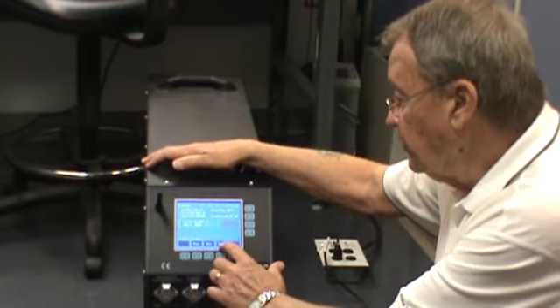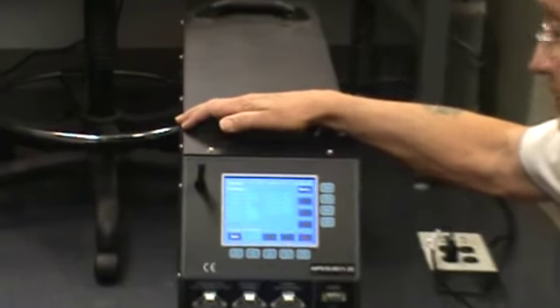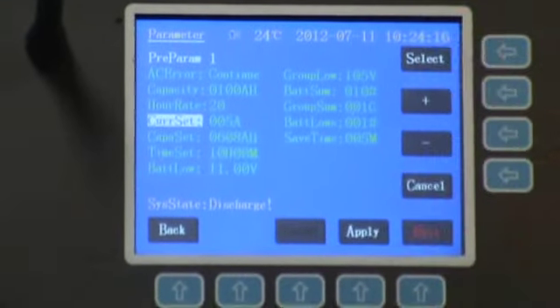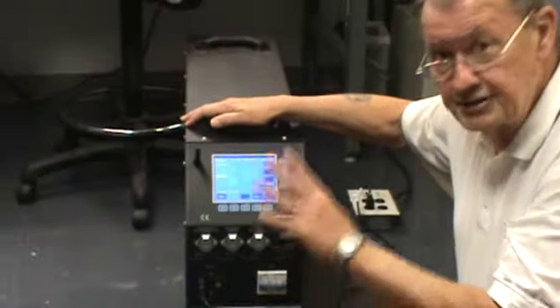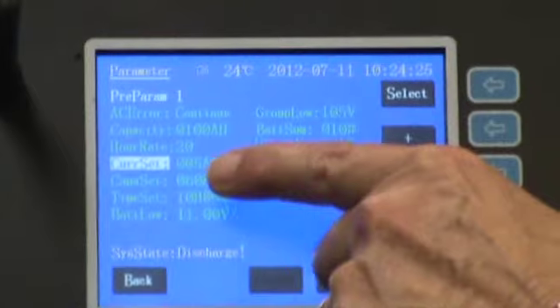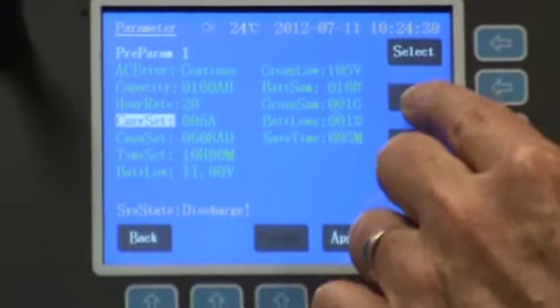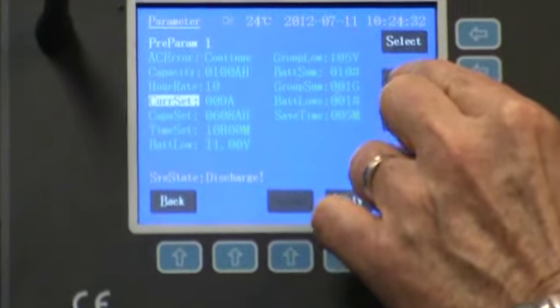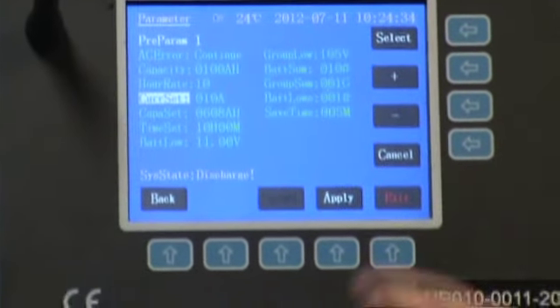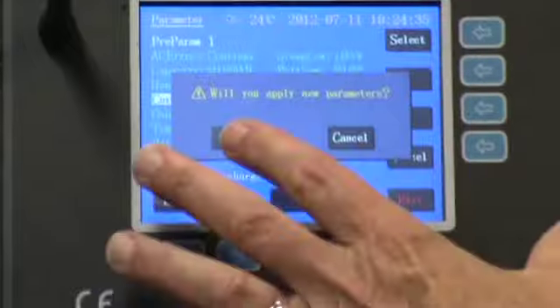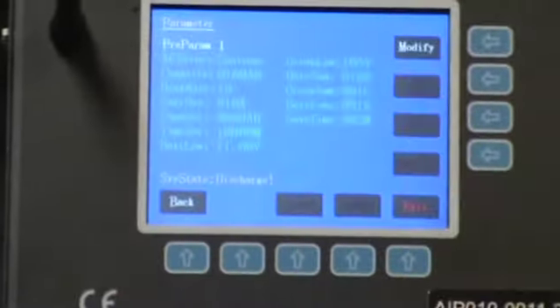For example, I can go into the parameter while it's running and move it down. Let's say right now we're running 5 amps, and I want to go to 10 amps while it's running. I go into modify, select, move it down to current set, and change that to 10 amps while it's running. I then say apply, and it asks if I want to apply those new parameters. I'll say yes, or okay.